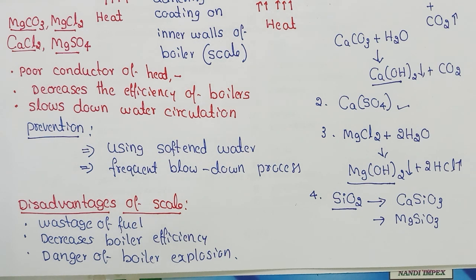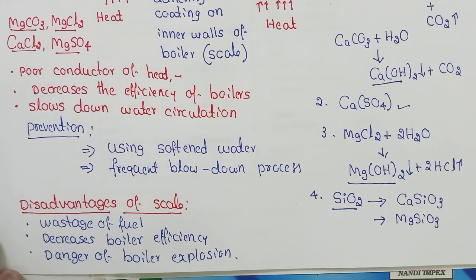In summary, scale and sludge formation in boilers is mainly due to the increase in concentration of salts. Sludge is caused by magnesium carbonate, magnesium chloride, calcium chloride, and magnesium sulfate. Scale is caused by calcium bicarbonate, calcium carbonate, calcium sulfate, magnesium chloride yielding magnesium hydroxide, and silicates. In the next video, we will discuss boiler corrosion. Thank you for listening to this video lecture on water chemistry — boiler feed water and scale and sludge formation.